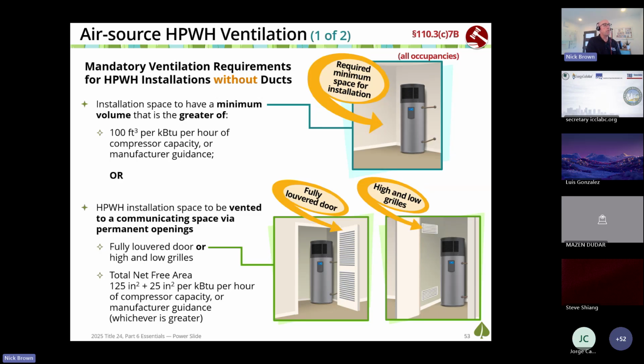Now, if you can't put it in a big enough space, like your garage would be a big enough space, a laundry room would most likely be a big enough space, then you need to put it in a place that's vented to another space via permanent openings so that it in effect is in a big enough room. That can be done with a fully louvered door or high and low grills. And the total net free area, either way, needs to be 125 square inches plus 25 square inches per kBTU per hour of compressor. Again, we need to know from the manufacturer's literature what the compressor capacity is. So if you see these heat pump water heaters put in small closets, make sure they have access to airflow governed by these two options.